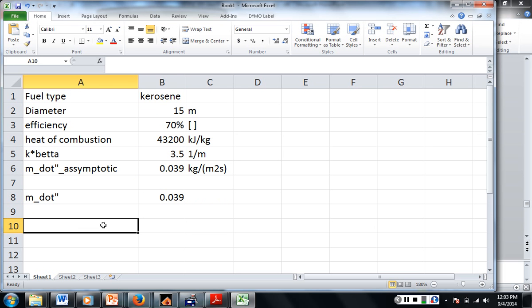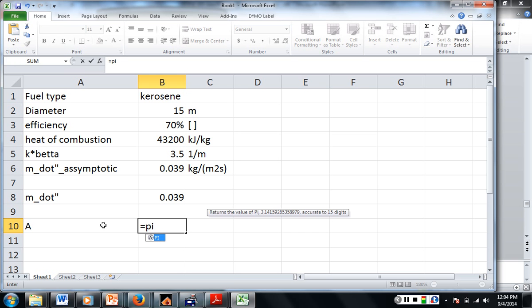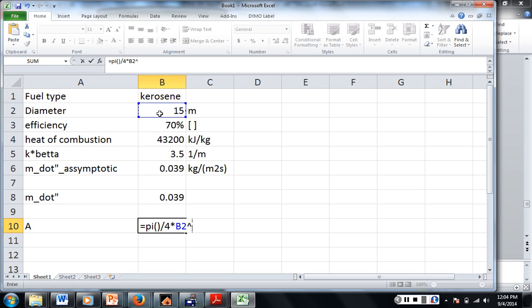Now to get our heat release rate, we need the efficiency which we have, the mass loss rate which we have, or mass loss flux which we have, the heat of combustion which we have, and the surface area. So area is equal to what? Pi over 4d squared. So in Excel, you can either put 3.14 or you can write pi, open parenthesis, close parenthesis, and that will give it the value of pi. Okay. Divided by 4 times our diameter squared.